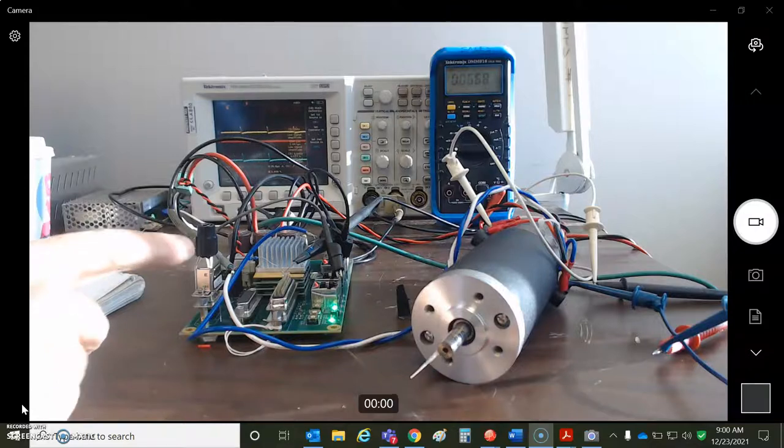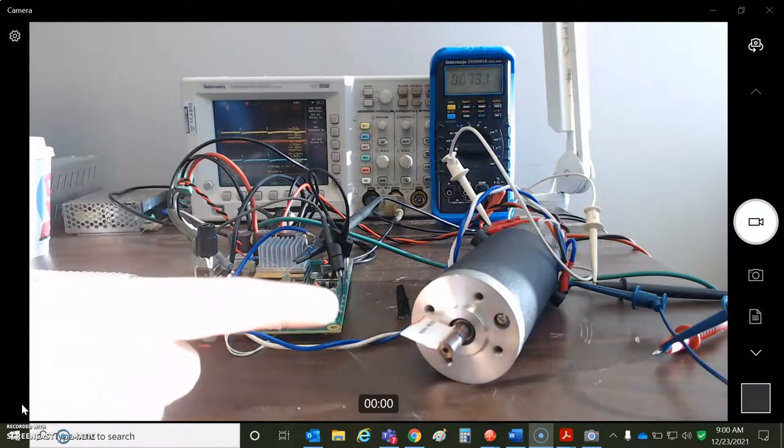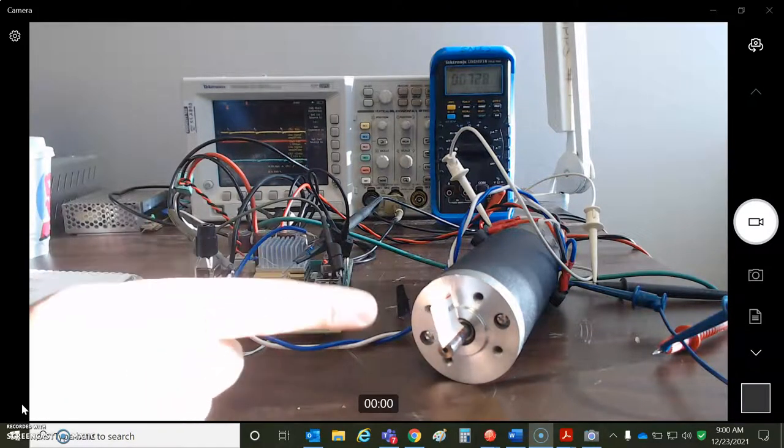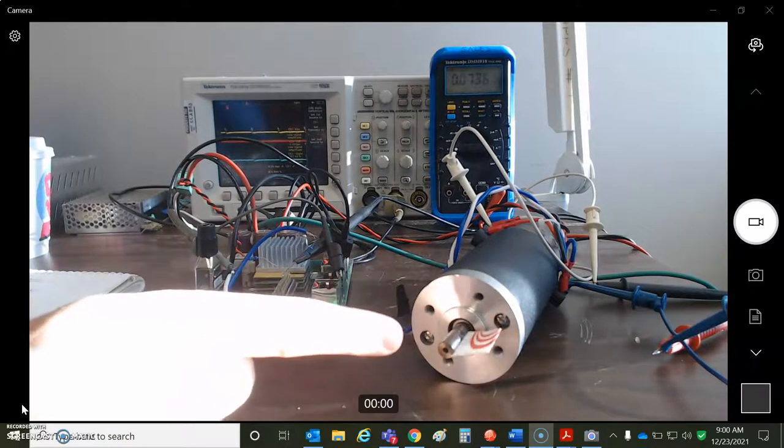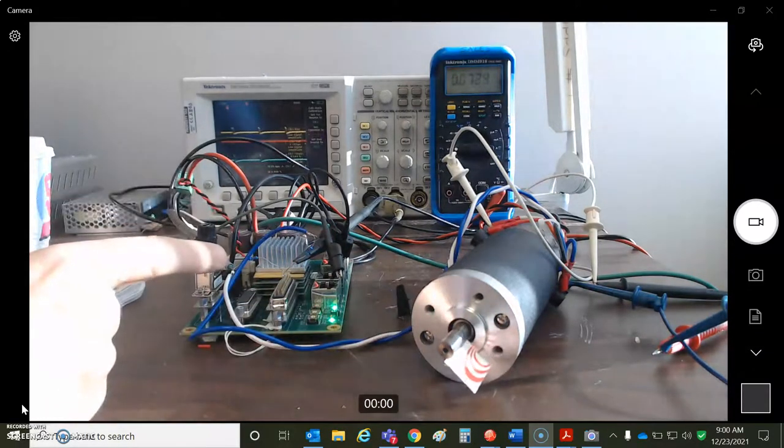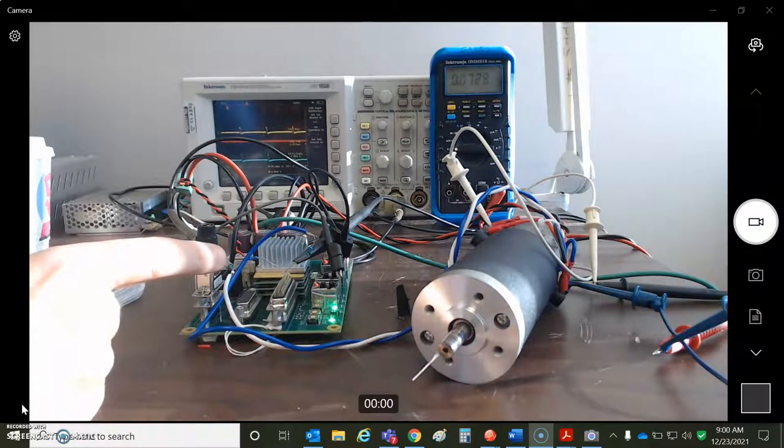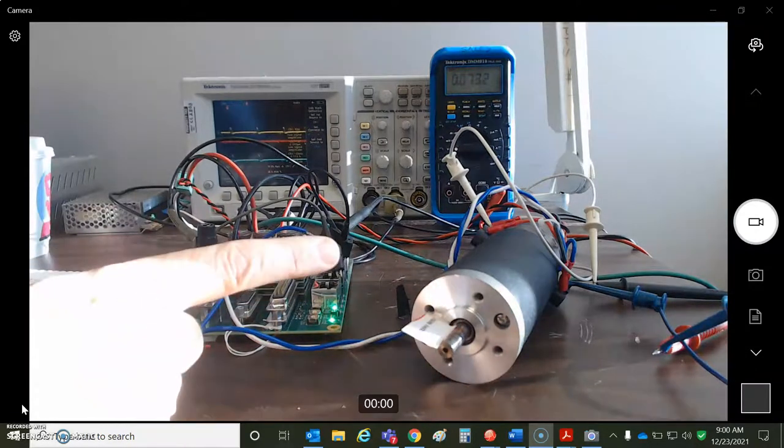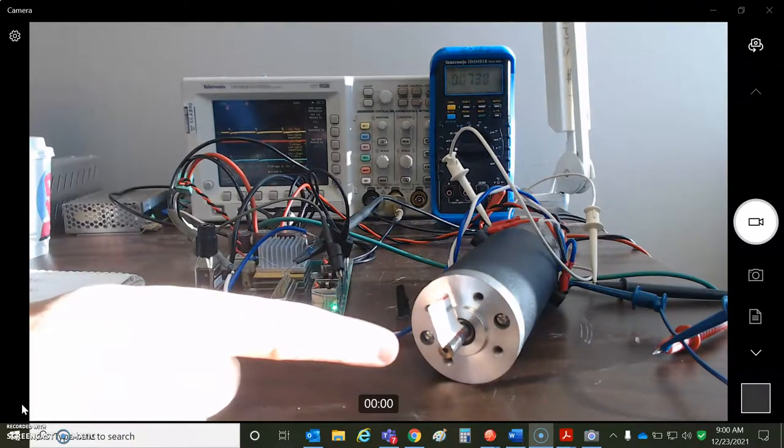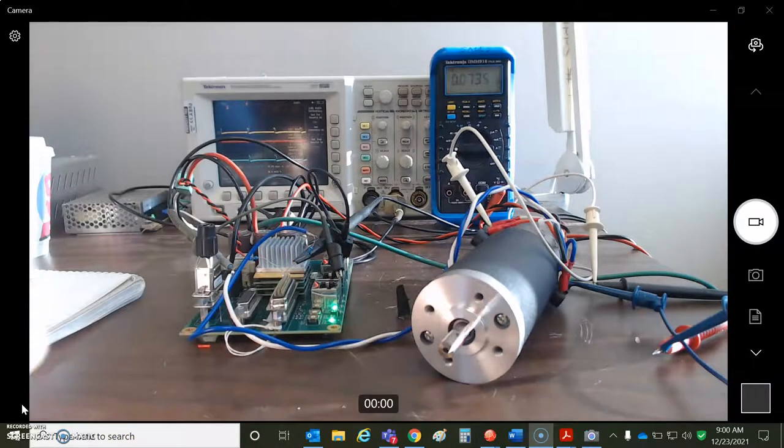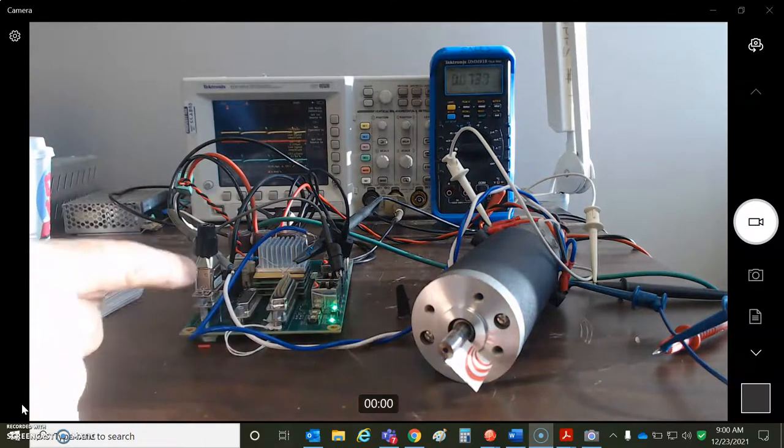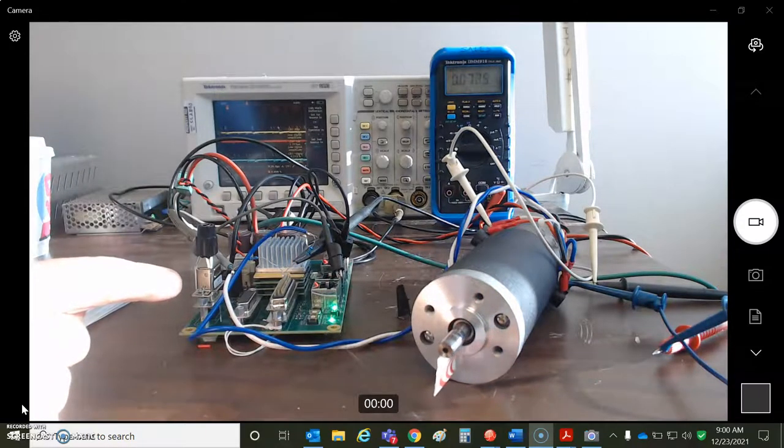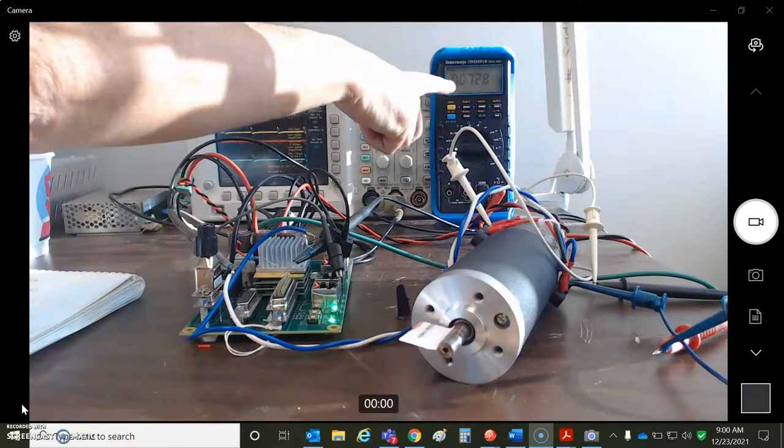I'll go into more detail in the note. But just the basic idea is I'm commanding zero velocity, yet my motor's rotating. So this nano has not been calibrated for offset. It's not a tachometer offset. When the motor's not spinning, you'll get zero volts. So this little bit of rotation is caused by the offset in the analog input having not been calibrated.